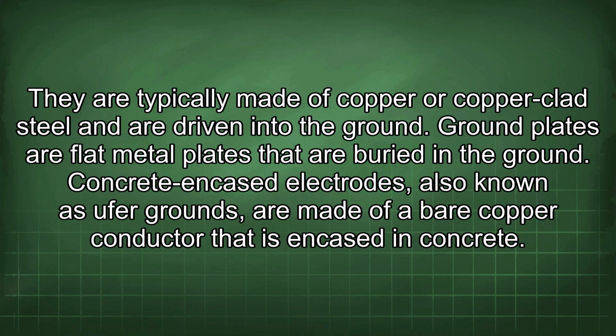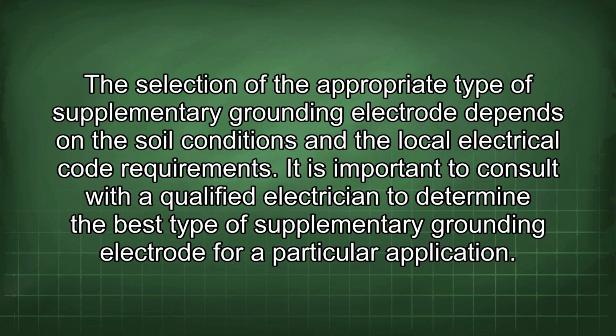Concrete encased electrodes, also known as Ufer grounds, are made of a bare copper conductor that is encased in concrete. The selection of the appropriate type of supplementary grounding electrode depends on the soil conditions and the local electrical code requirements.